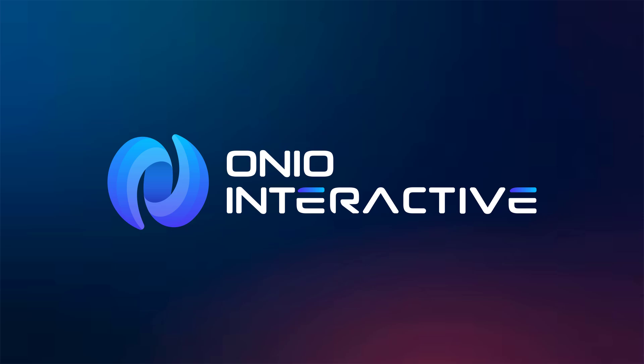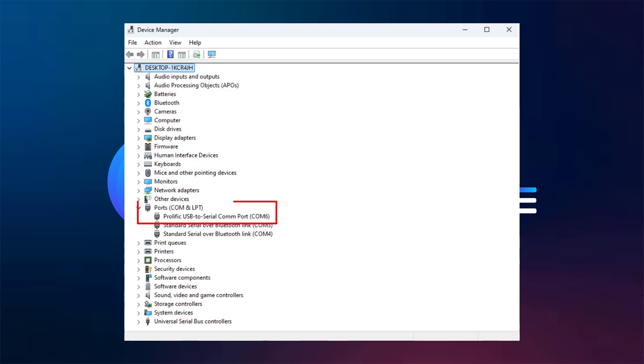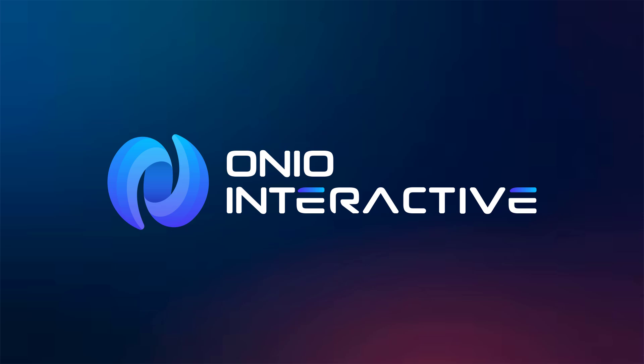Start by connecting your adapter to your computer, and open Device Manager to confirm that it has been recognized. If it shows up correctly, proceed to wire the RS-485 side of the adapter to your device, making sure that pin A is connected to A and pin B is connected to B. Once the connection is in place, our first step will be to identify the slave address of the device.